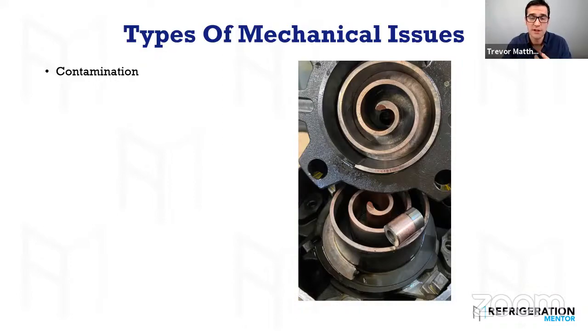Moisture, because moisture, water, and heat cause acid inside the system with POE oil. Most systems now, like commercial refrigeration, have POE oil, and you're seeing it more and more with all the manufacturers and the new refrigerants. You have POE oil, and there are other blends of polyester oils, but when you add moisture to it, it causes acid because POE is made of acid.